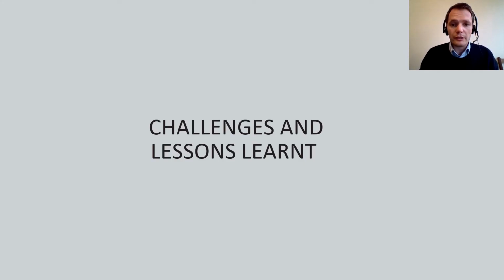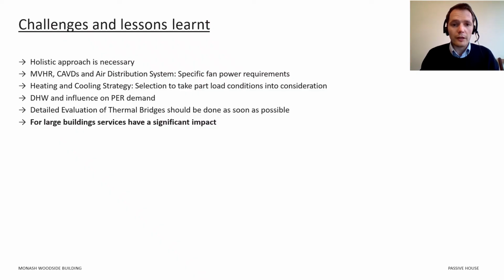So what are the key challenges we experienced and what key lessons did we learn? A holistic approach is necessary. Mechanical ventilation units with heat recovery, constant air volume dampers, and a well-designed air distribution system is required to meet the specific fan power requirements.